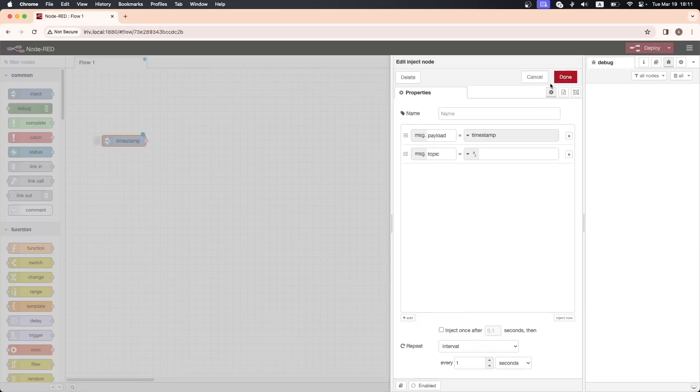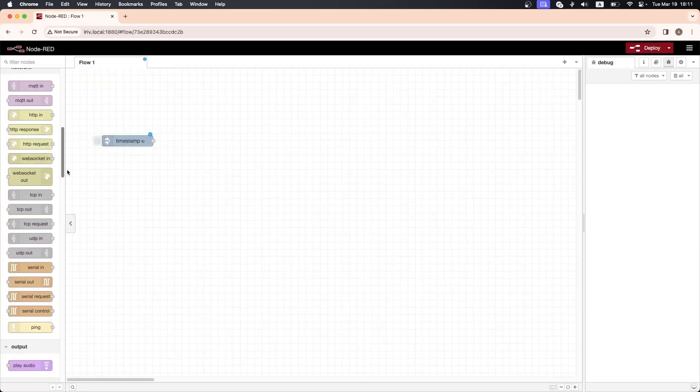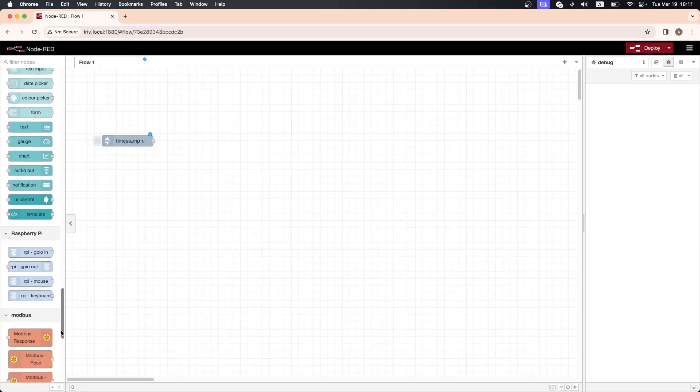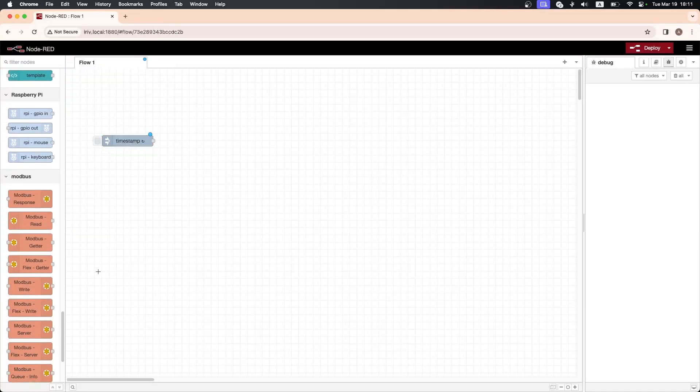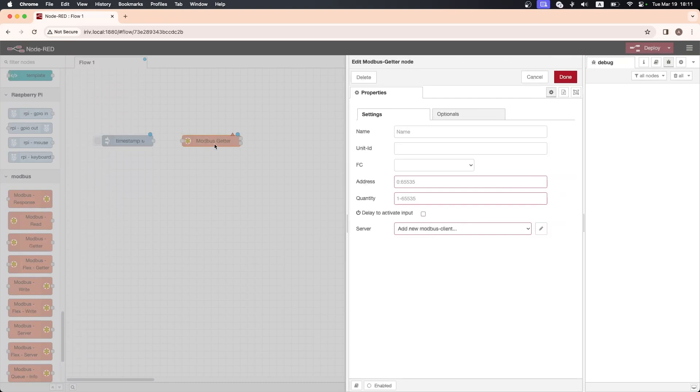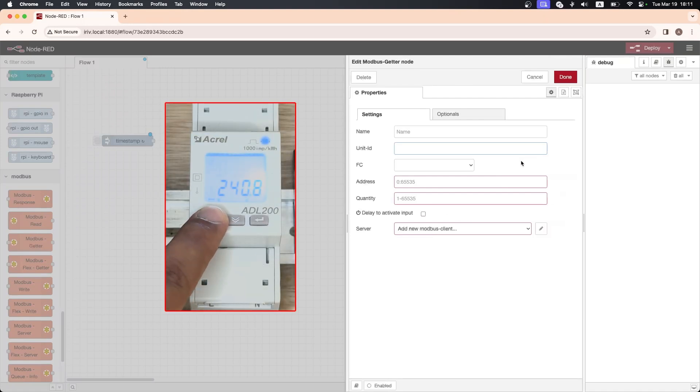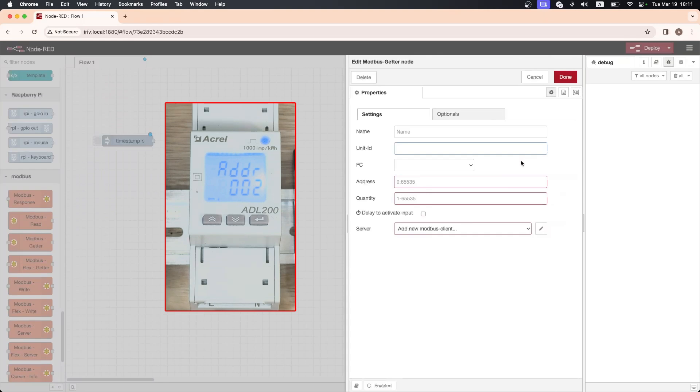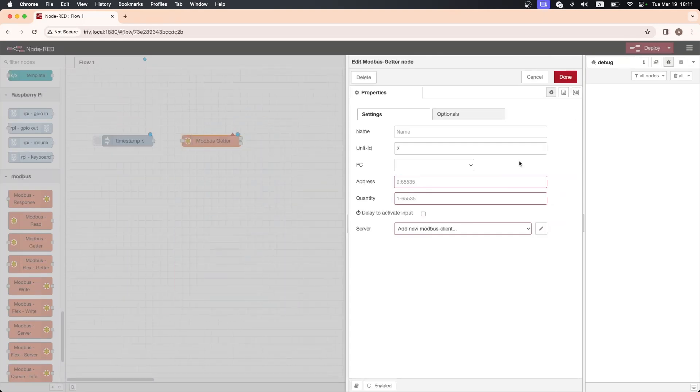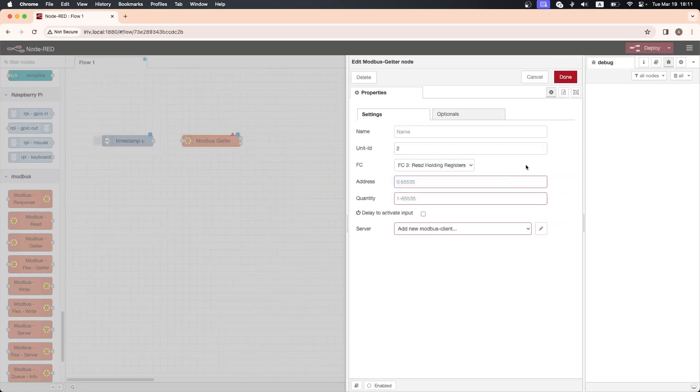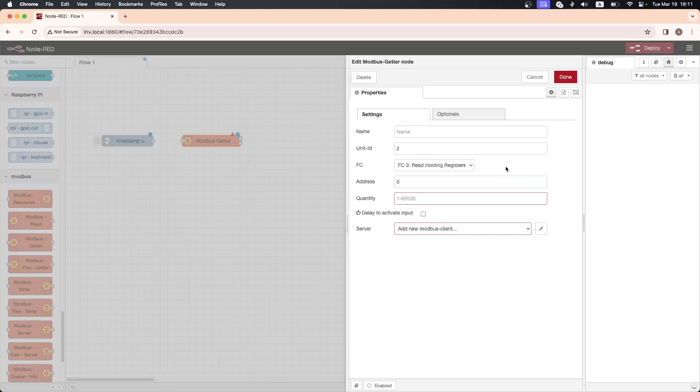Next, drag and drop ModBus getter node and open its properties window. The first setting we have here is Unit ID. This identifies the ModBus device we are communicating with. Navigate through your power meter settings to locate the Unit ID. In my setup, the Unit ID is 2. This is the function code which specifies the type of ModBus function. Choose function code 3 to read holding registers.